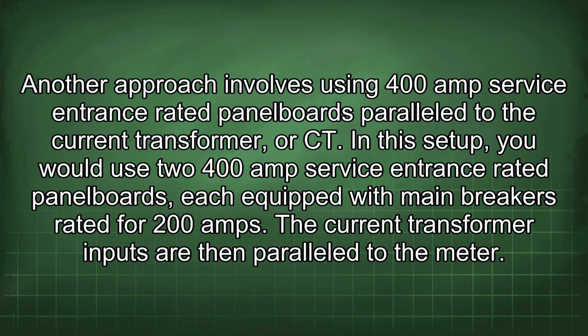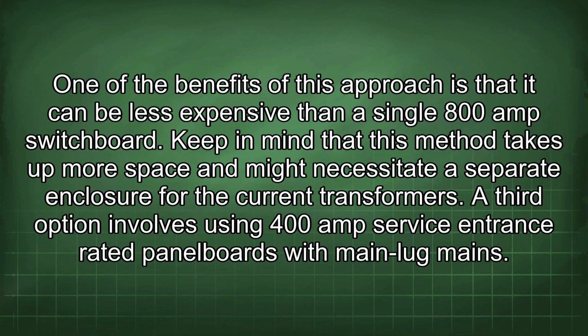Another approach involves using 400 amp service entrance rated panelboards in parallel to the current transformer, or CT. In this setup, you would use two 400 amp service entrance rated panelboards, each equipped with main breakers rated for 200 amps. The current transformer inputs are then paralleled to the meter. One of the benefits of this approach is that it can be less expensive than a single 800 amp switchboard. Keep in mind that this method takes up more space and might necessitate a separate enclosure for the current transformers.